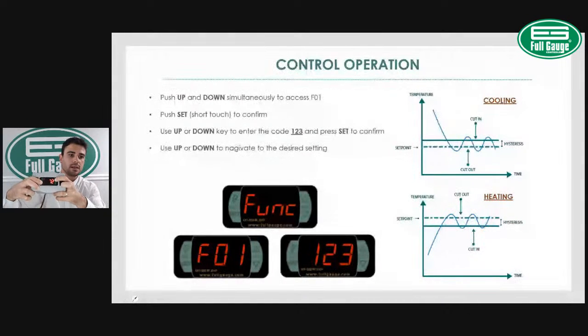Because here I want to show you one thing. I've got my compressor indication LED on, right? There is this indication LED on. Now I'm going to switch to 90. Here you go. My compressor just went off because my display temperature is within that set point condition. Once it goes back, you're going to see what temperature is being read at the controller. Here we go, and we got 85 degrees. So you see, my compressor just went off. So that's how you change the settings on any of the Full Gauge controllers, just by pushing up and down simultaneously and entering the code 123.